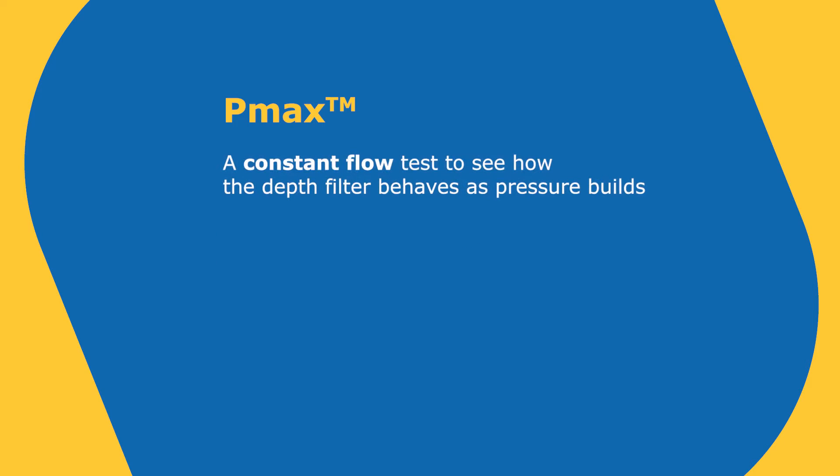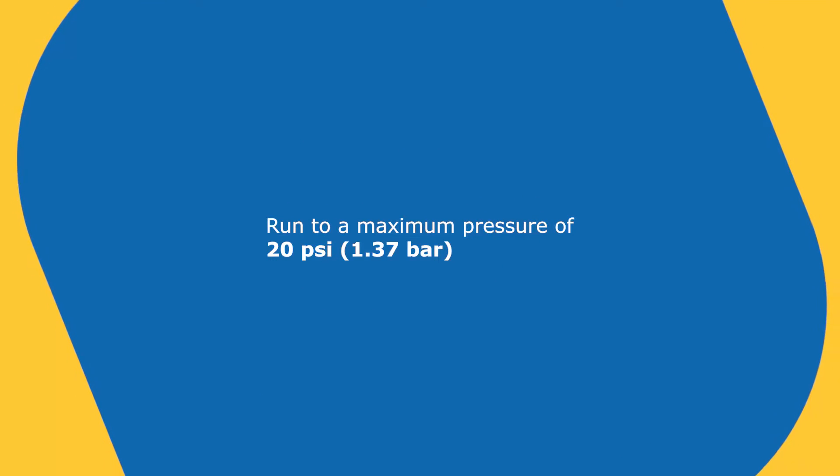A PMAX experiment is a constant flow test where you're running at continuous flow rate, and you're going to collect information to see how the depth filter behaves as it builds up pressure. So you want to run it to a maximum pressure of 20 psi, and you would be collecting data that I'll discuss later in the video.